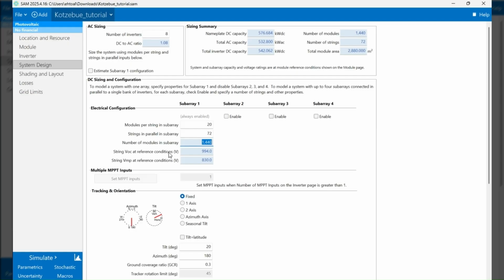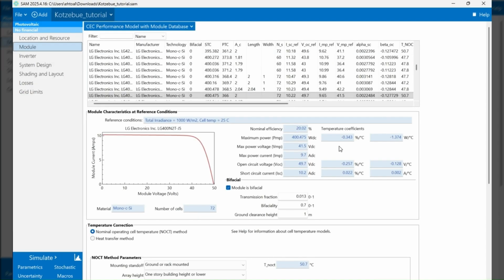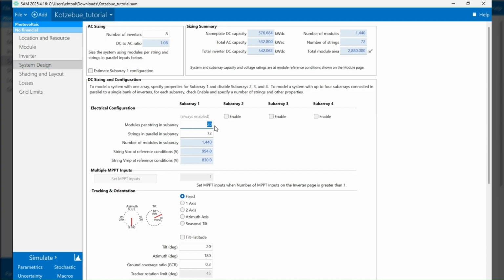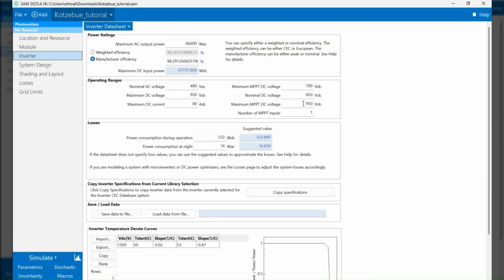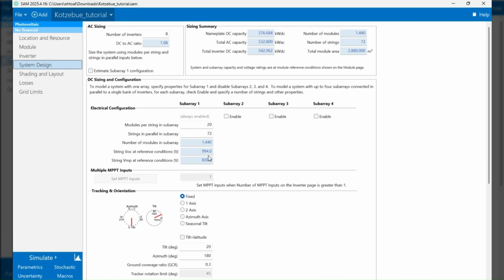The open circuit voltage for the modules per string is just the defined open circuit voltage in the module page for the specific modules that we picked, multiplied by the number of modules in series. And so that gives you this value right here, which should always be lower than our maximum DC voltage defined under the inverter. And then if we go over here, we can see that this value, the maximum power point voltage, is also automatically calculated.